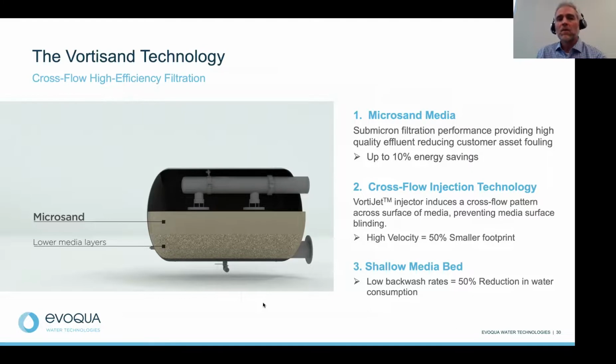Now let's talk about the Vortisand technology in a little bit more depth. Vortisand is very different than a multimedia technology. Vortisand uses a silica-based media, but it's a very fine media that we call microsand. It's about 0.15 millimeters in diameter. So we're talking about very, very fine sand, comparatively to maybe 2 or 3 times that of a multimedia. And with such fine sand, we are able to achieve very high quality effluent that ultimately will have great impact on reducing customer asset fouling, right, what I talked about earlier.